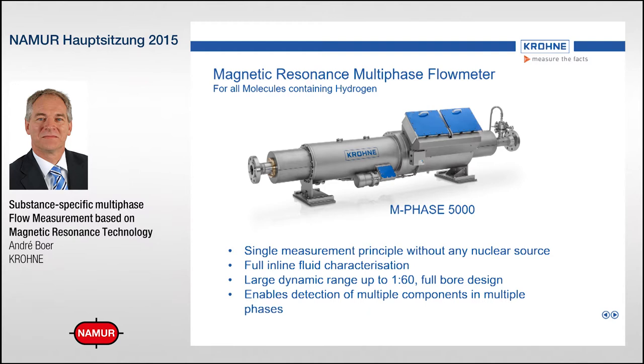By using magnetic resonance, an inline fluid characterization can also be done, which means that you can install the instrument without any further parameterization or calibration and actually characterize the liquid or gas going through it. The flow meter has a very large dynamic range with a scale of 1 to 60. It's a full bore design with no moving parts inside or anything protruding inside the pipe.